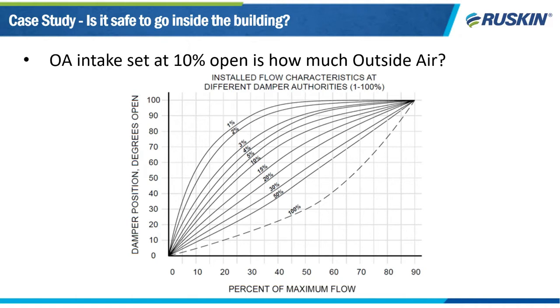With both the return air and the outside air damper open, only the air that is leaving the space will be pulled in through the outside air opening. So that air has got to be exhausted through exhaust fans or bathroom exhaust or whatever. So it's generally not very much air that's coming in. And when this is the situation, the position of the outside air damper will have little effect on how much air comes into the building.